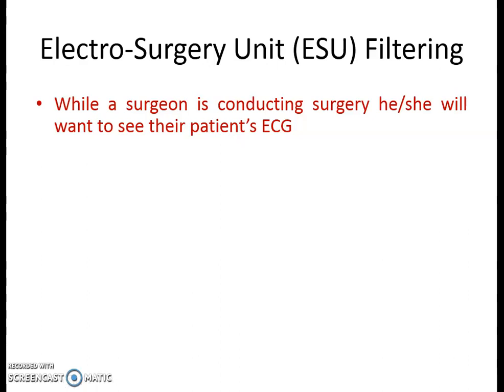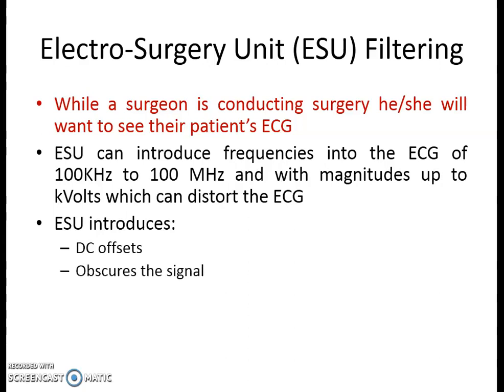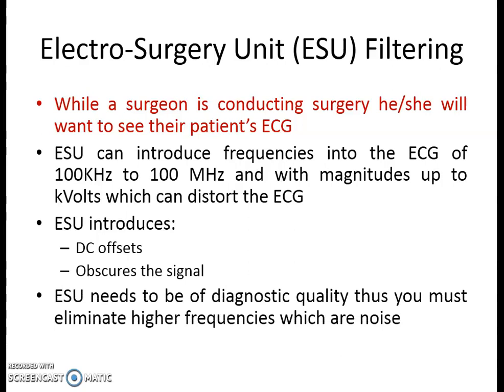Regarding ESU filtering: while the surgeon is conducting surgery, he or she will want to see the patient's ECG. The ESU (Electrosurgical Unit) is a machine generally used for cutting and coagulation with a high frequency signal in the range of hundreds of kilohertz up to several megahertz, with a magnitude in terms of kilovolts. So this signal can also distort the ECG. The ESU can introduce two types of error: it can introduce a DC offset, or it can completely obscure the ECG signal. So the ESU needs to be of diagnostic quality.